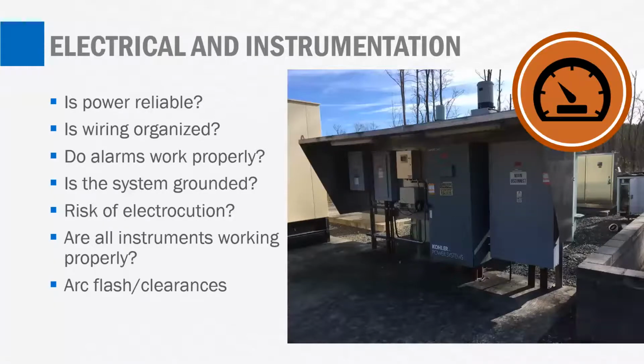Electrical and instrumentation. Do you have reliable power? Is there a permanent generator? Do you have portable generator hookups? When you open these panel boxes, is there spaghetti wiring? Is it something that can be easily worked on if necessary? What about your alarms? Some of these pump stations have auto dialers for alarms. Is that auto dialer system working properly? Are your audible and visual alarms working?